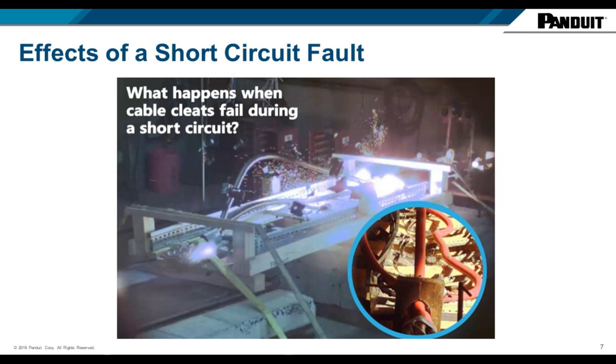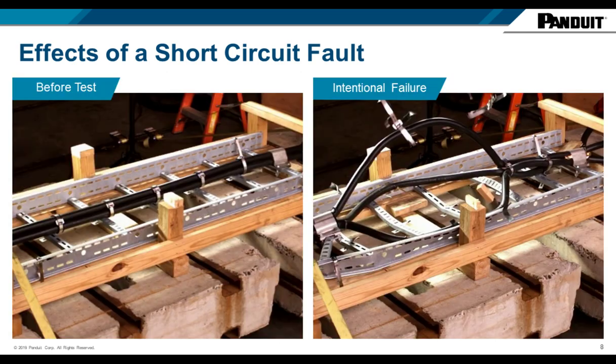The following pictures, from very high-speed resolution cameras during testing, show what happens when a cleat fails — fortunately captured in a lab setup — illustrating the violence of the electromagnetic force. This slide shows a cable cleat test rig fixture more clearly. You can see that the cables are neatly contained within the ladder rack and cable tray, aligned, and everything is safe as it should be.